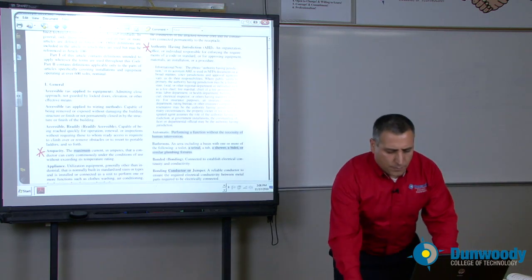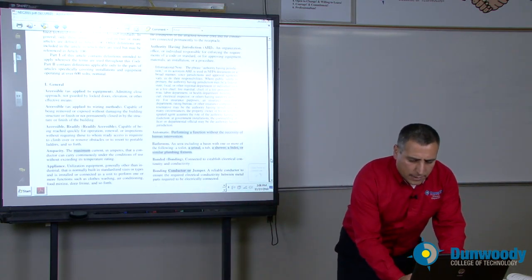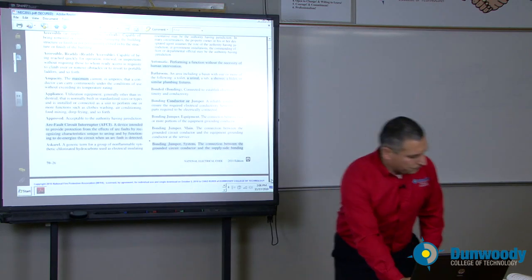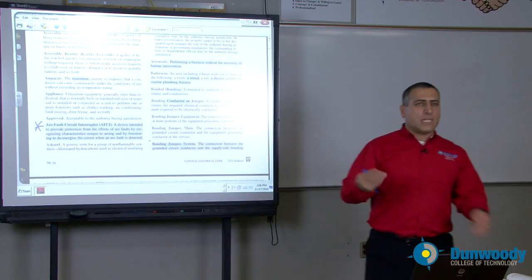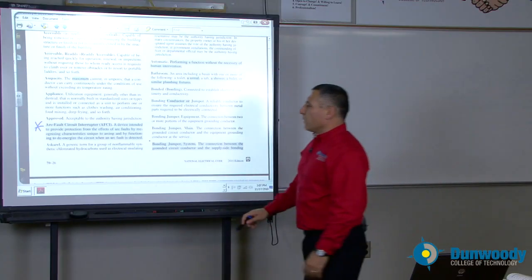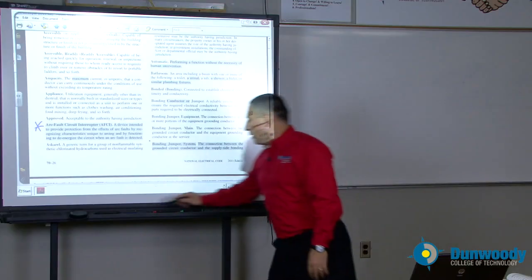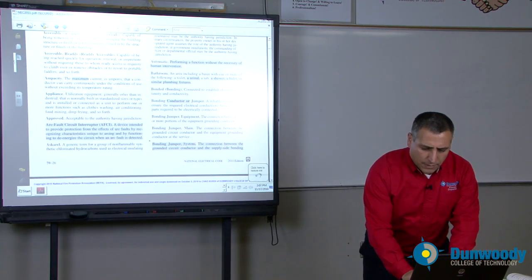The second topic I'm going to highlight is arc-fault circuit interrupters. Arc-fault circuit interrupters were brand new in 2008. If you have an arc in a circuit, these are electronically designed equipment that senses that there is an arc and interrupts it. It's a device intended to provide protection from the effect of an arc-fault. You're going to hear that receptacles in a bedroom in a residential application need an arc-fault — a circuit breaker that trips in case of an arc, line to line or line to ground.